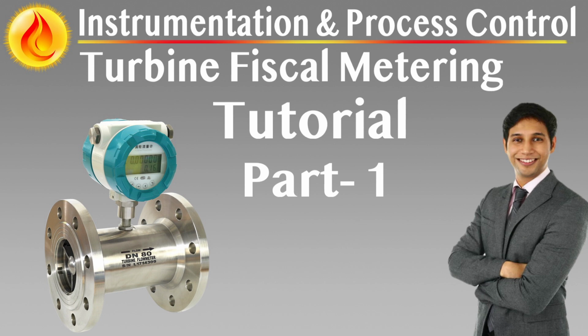Meter prover integration and calibration assurance. Prover type selection and compliance. The meter prover is a critical calibration component that ensures the metering system's traceability and legal acceptance. Unidirectional or bidirectional mechanical displacement provers are standard, as defined in API MPMS Chapter 4. For offshore or space-constrained facilities, compact provers may be used if approved by both fiscal authorities and the project principal. Regardless of type, the prover must be integrated downstream of the metering runs and be representative of the same process conditions as the meters it calibrates.